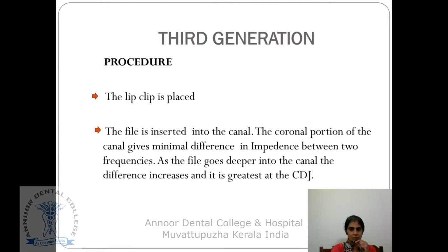The procedure is that there is a lip clip, to be used like how we do it in the first generation. The file is slowly inserted into the canal. The coronal portion of the canal gives a minimal difference between the impedance values of the two frequencies.